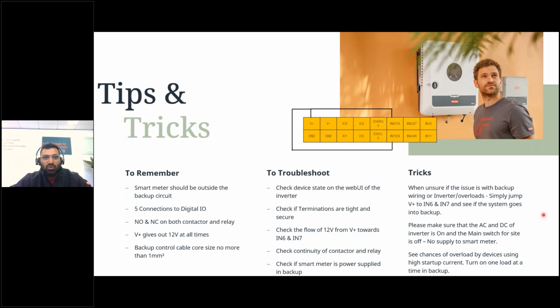So if it says no feedback from relay, that is IN7, which is feedback from relay. If it says no feedback from contactor, that is IN6. So you just make sure they are plugged in properly. And what else can we do? We know that all we're trying to do is get this 12 volt coming from V+ to reach IN6 and IN7, but it goes through this contactor and relay. So we can check where we are losing this 12 volt.